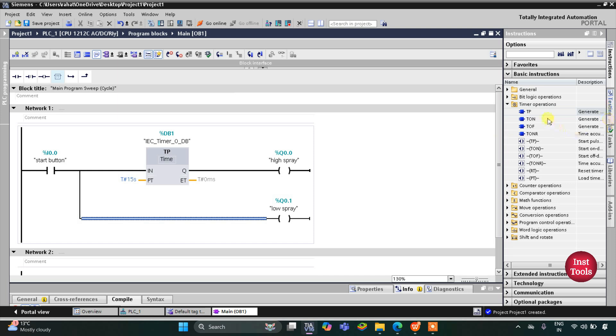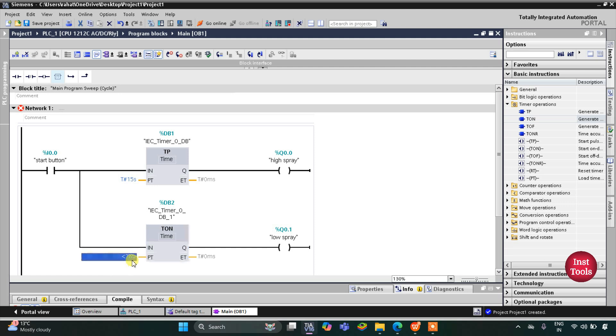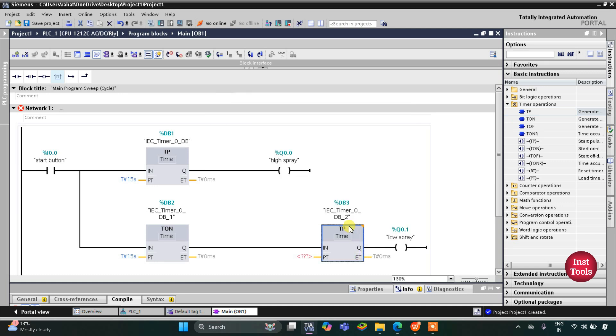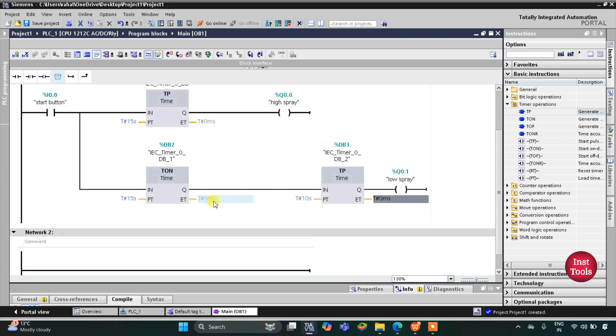For the low spray delay, I will use a TON here with a preset value of 15 seconds. Then this low spray will operate for 10 seconds, so I will insert a TP here with a preset value of 10 seconds. So when the start button is pressed, there will be a high spray for 15 seconds, and after 15 seconds there will be a low spray for 10 seconds.